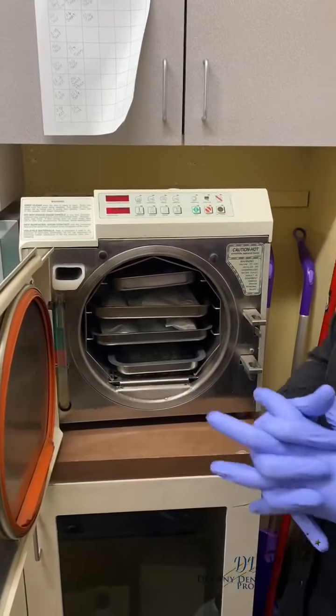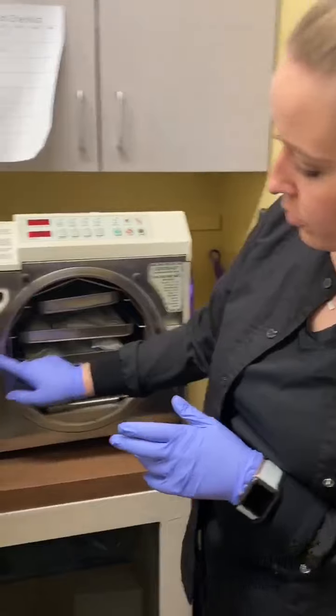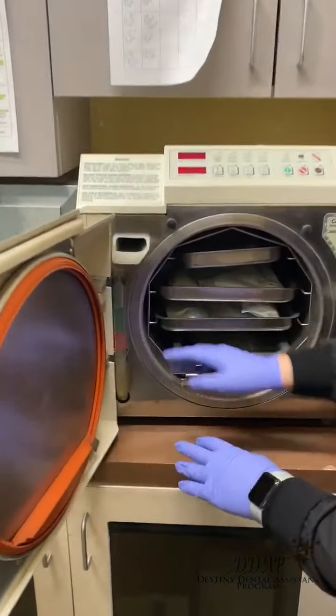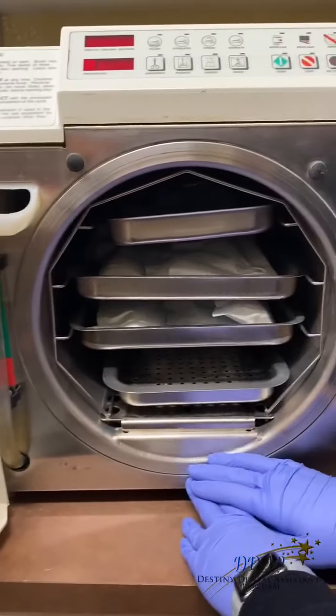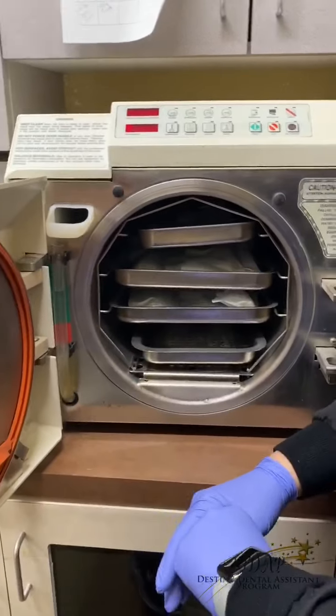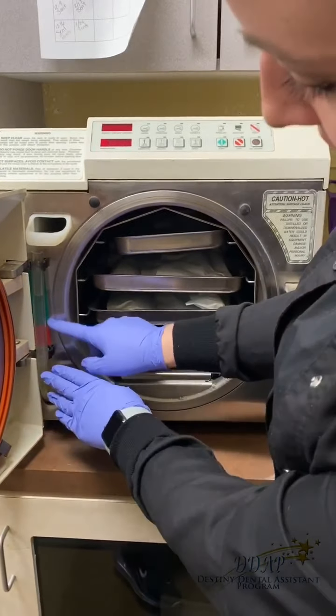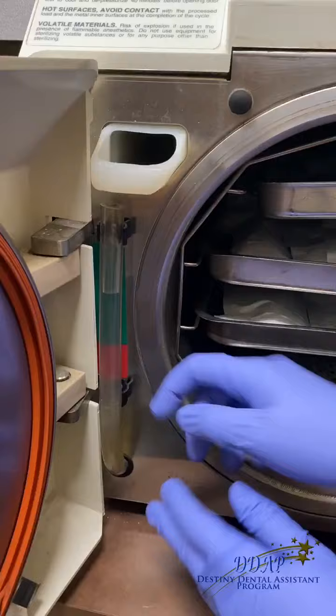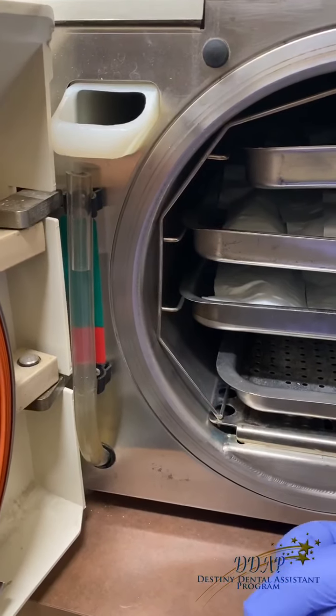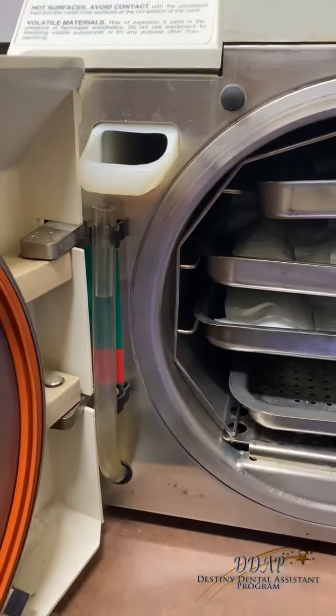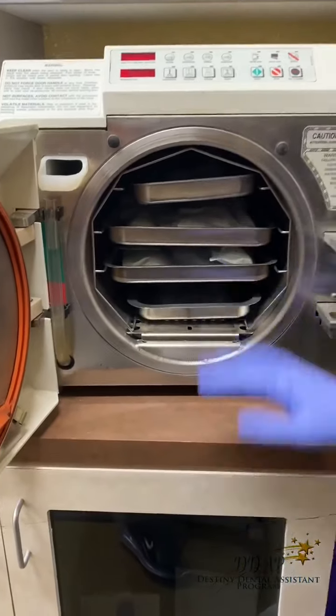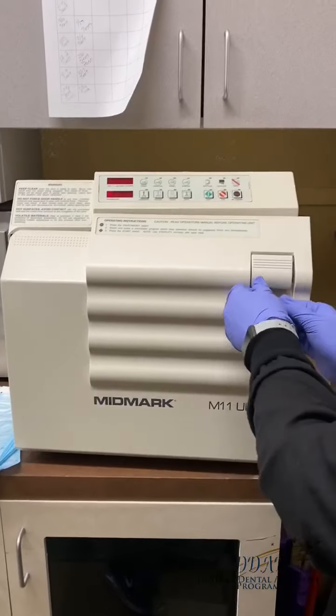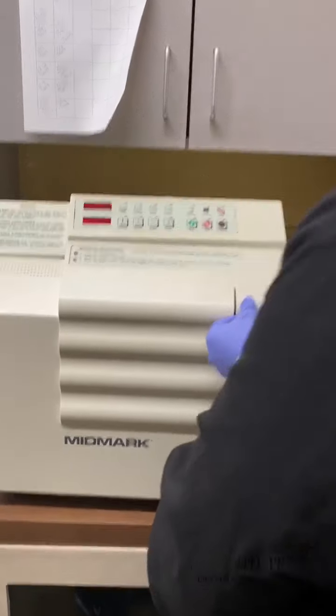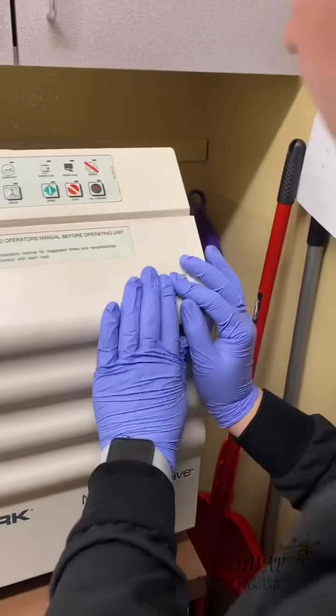A couple things we want to make sure of before we start the autoclave is that our water line is correct. We always fill the autoclave with distilled water. You will never use anything but distilled water. So it needs to be between this green line. The red line will show you that it's needing more, and then you fill the water up in here. So once I've noticed that everything is good, I can go ahead and close it. This door is a little harder to close, so you lift up, you push in, and then it will lock in place.